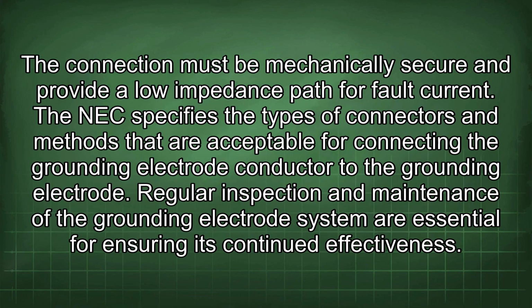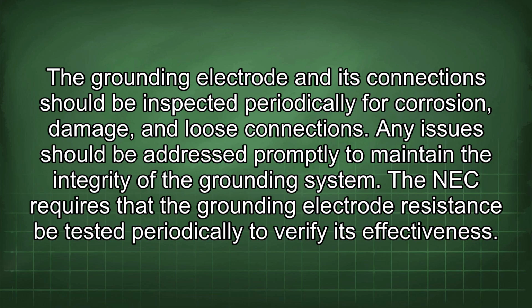The connection must be mechanically secure and provide a low impedance path for fault current. The NEC specifies the types of connectors and methods that are acceptable for connecting the grounding electrode conductor to the grounding electrode. Regular inspection and maintenance of the grounding electrode system are essential for ensuring its continued effectiveness. The grounding electrode and its connections should be inspected periodically for corrosion, damage, and loose connections. Any issues should be addressed promptly to maintain the integrity of the grounding system.